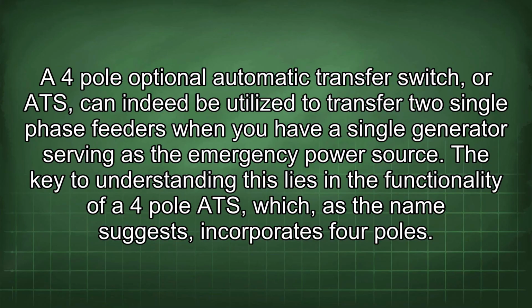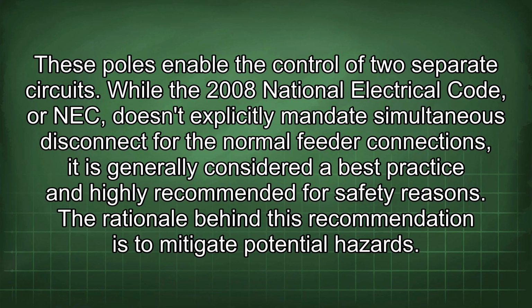A 4-pole optional automatic transfer switch, or ATS, can indeed be utilized to transfer two single-phase feeders when you have a single generator serving as the emergency power source. The key to understanding this lies in the functionality of a 4-pole ATS, which, as the name suggests, incorporates 4 poles. These poles enable the control of two separate circuits.